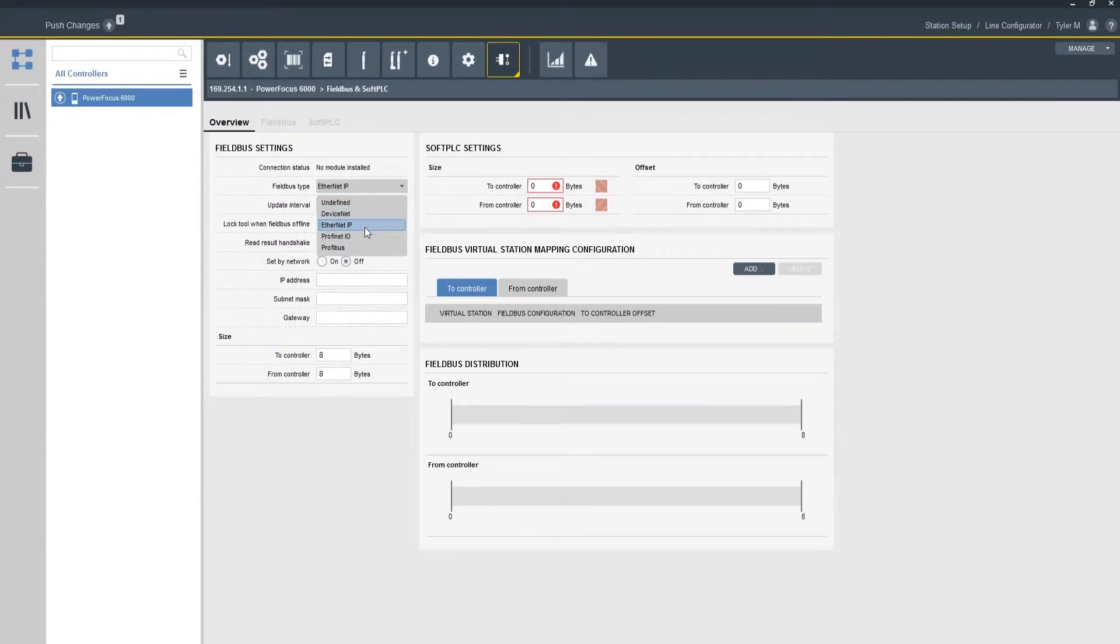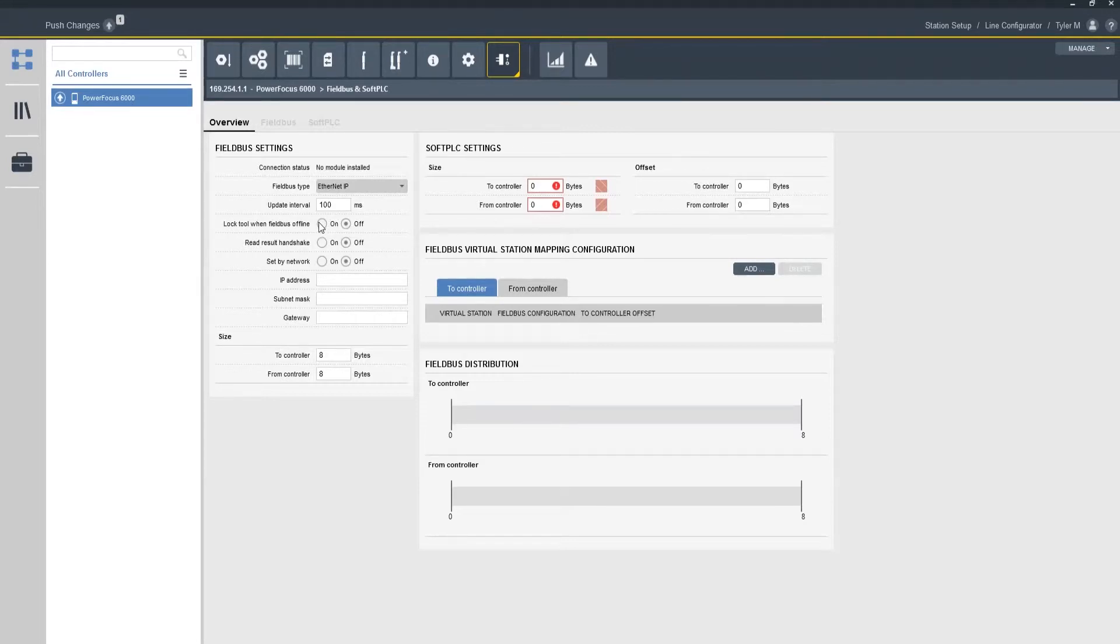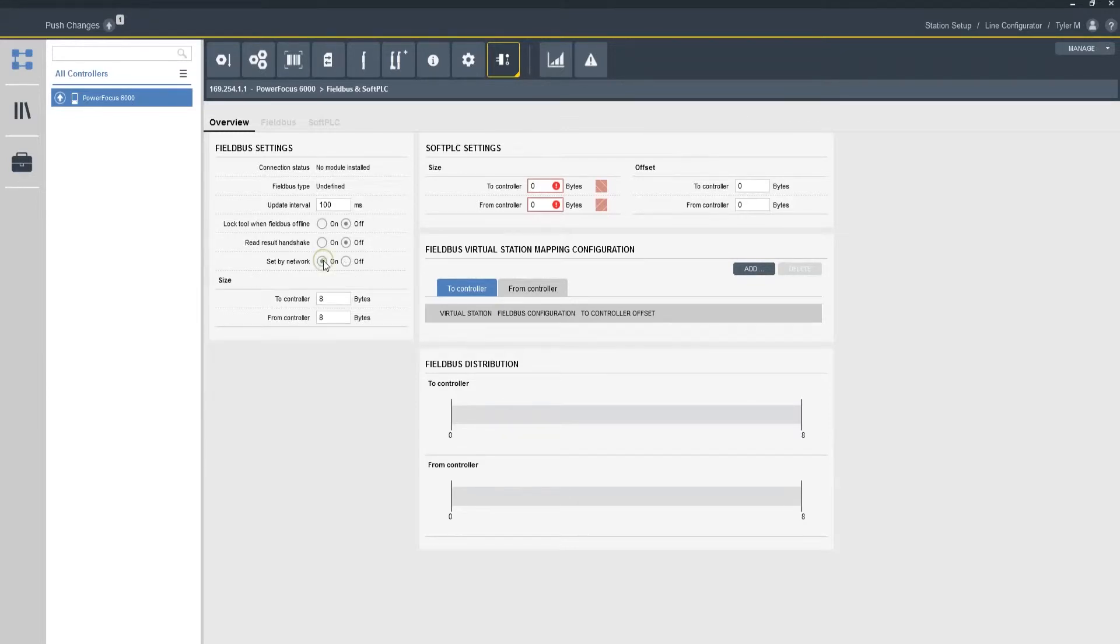So let's just say for training purposes that we're using Ethernet IP. So I'm going to select Ethernet IP, I'm going to set my update interval. I also have a couple generic settings such as lock tool when field bus offline, read result handshake, and we can also set our IP address from the EIP network.